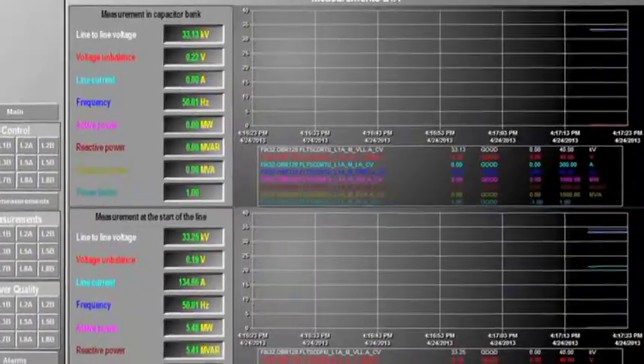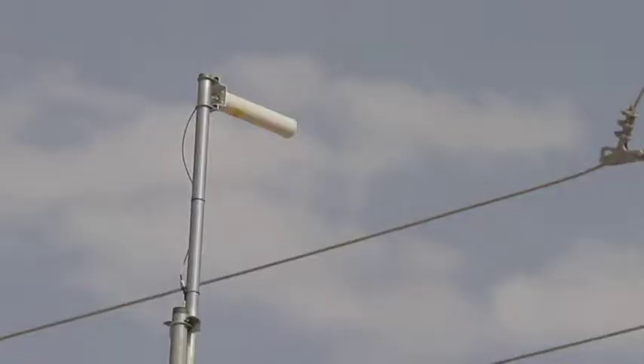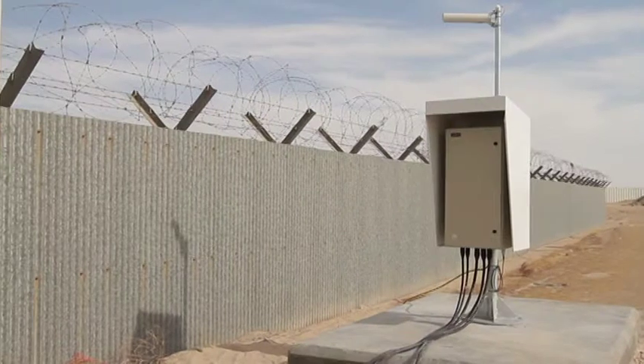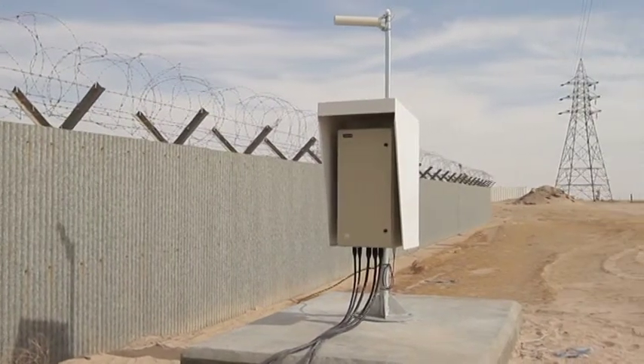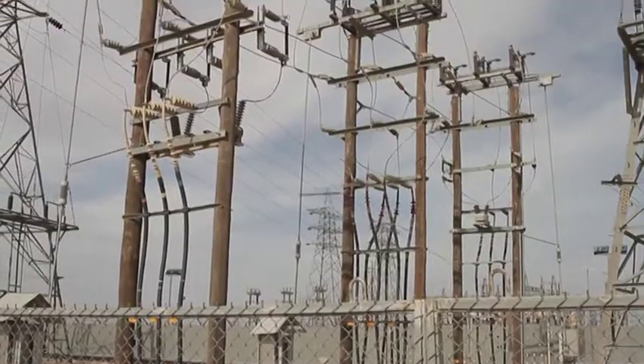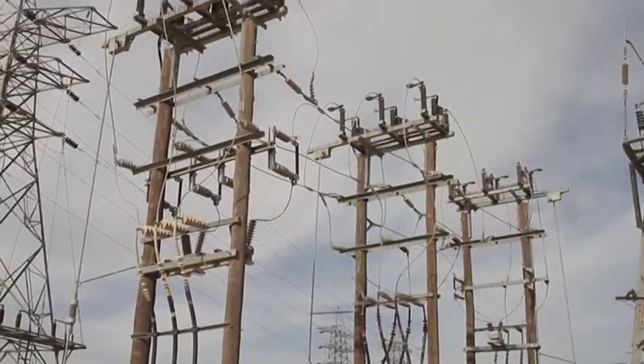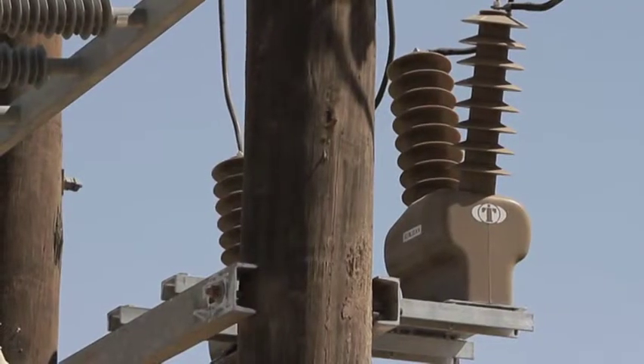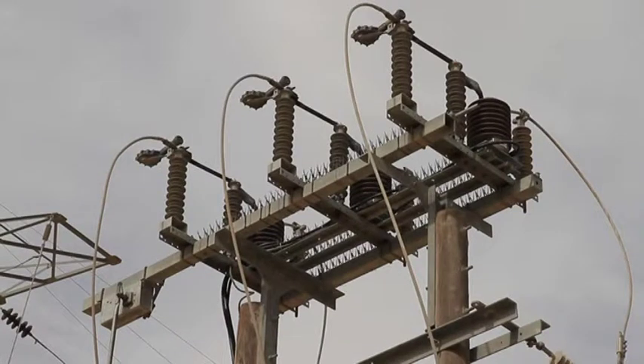Harmonic filter banks can be operated either automatically or remotely from the central control room, according to load conditions in each of the distribution feeders. The control algorithm maximizes power factor and limits harmonic distortion on each feeder for any load condition.